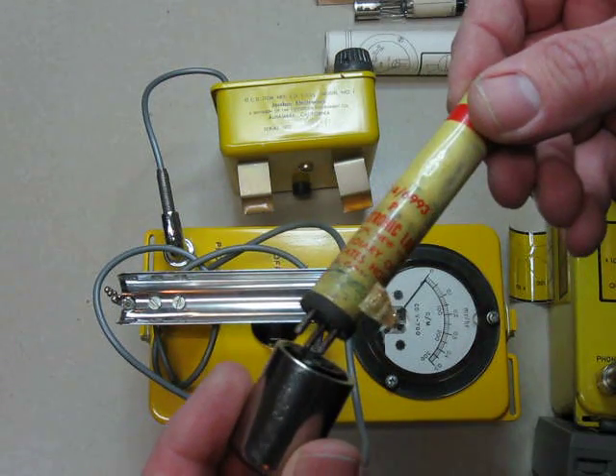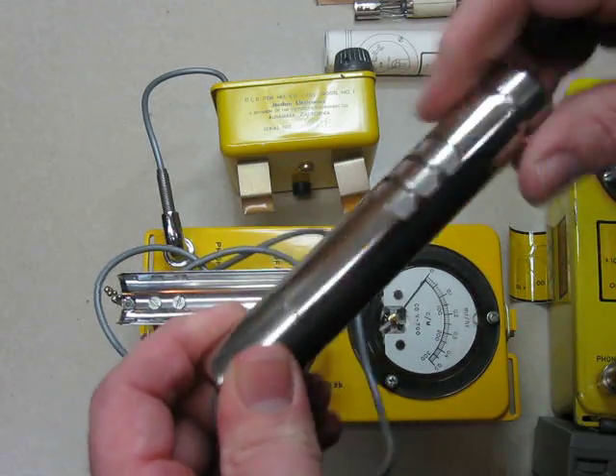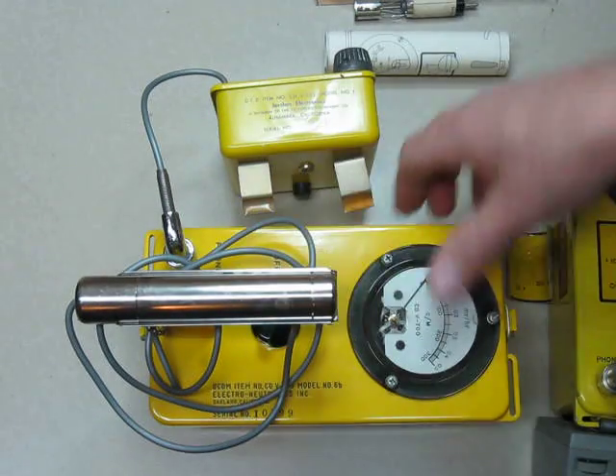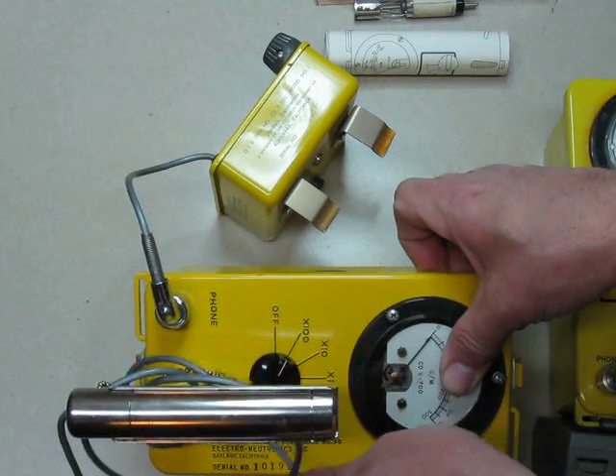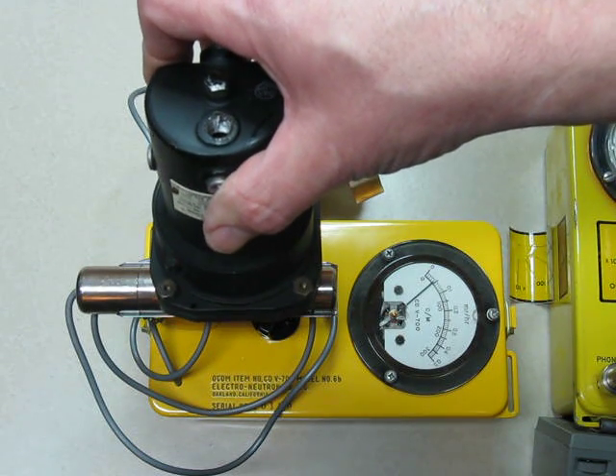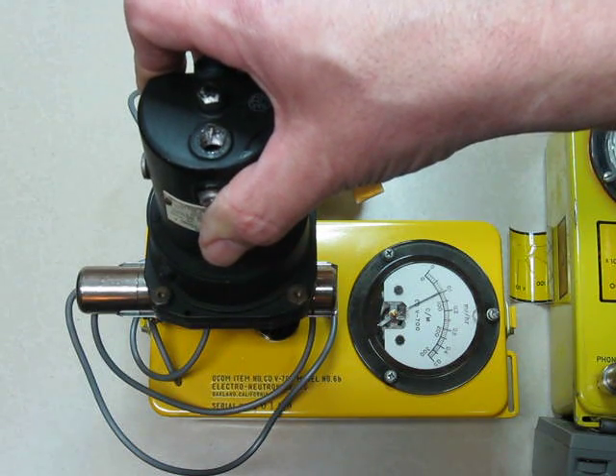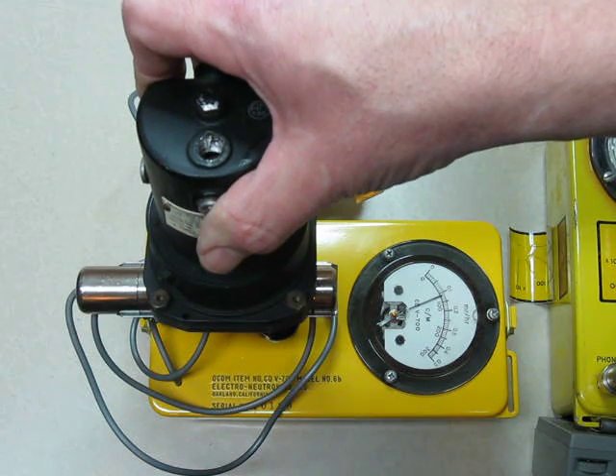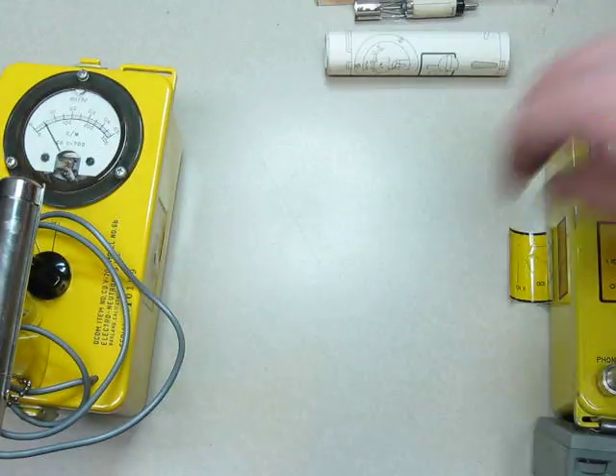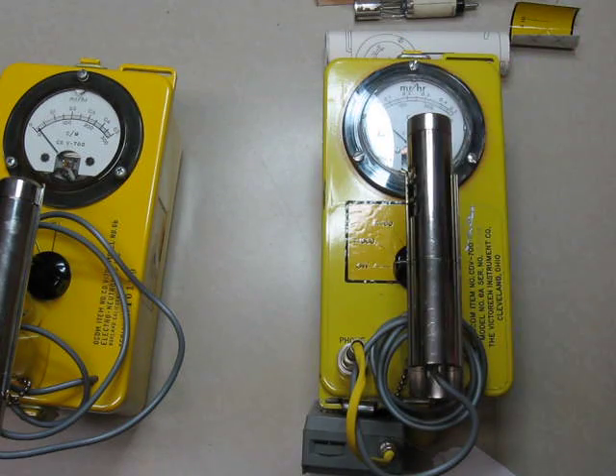We'll put our old 6993-2 back in there and turn it back on. We're going to the x100 scale here. Hear the click volume is substantially increased. We'll go up to about 10. That's the Electro-Neutronic 6B. And this is a Victoreen 6A. That tells me the conversion is just a tube and a sticker.